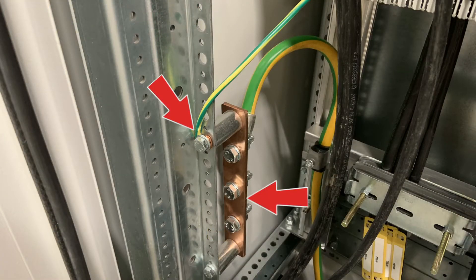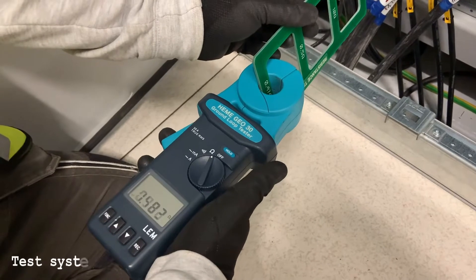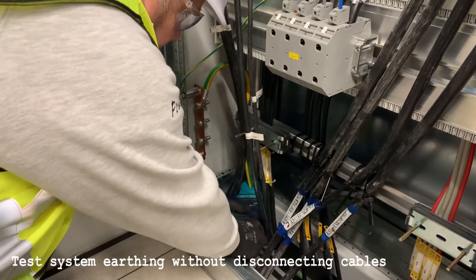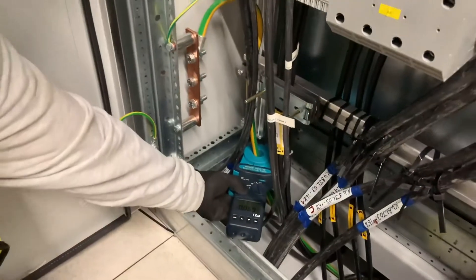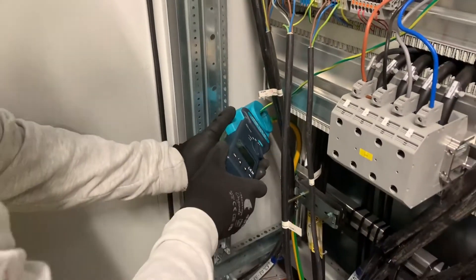As this installation is still ongoing, firstly we have to check the effectiveness of the earthing system. We use this HEME GEO 30 ground loop tester, first conducting a calibration check to make sure the instrument is working correctly, and then we place it on the main cable going down to the substation PE bar. We've got a reading of 0.069 ohms, so it means this cable is connected. As a matter of interest we just clipped it on the cable coming from the temporary supply, which gave us 0.9 ohms. Happy that the earthing system is intact.